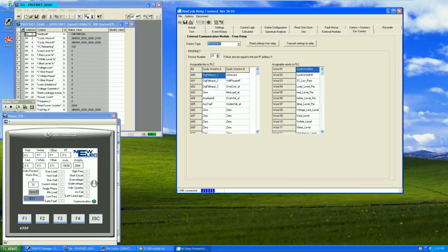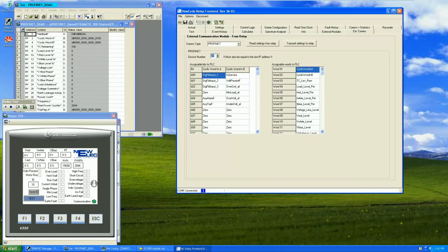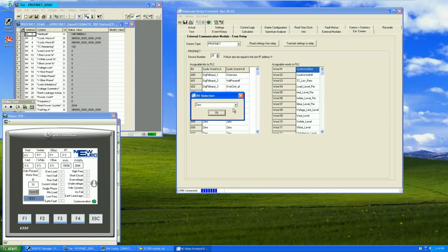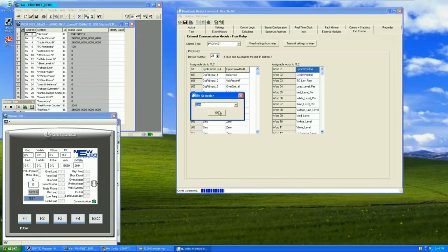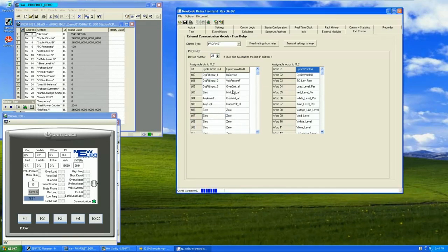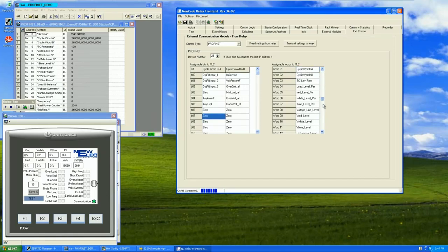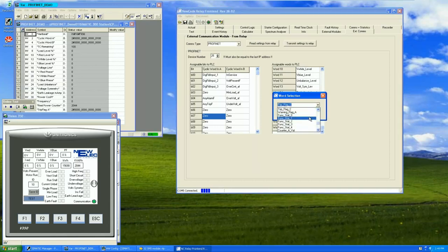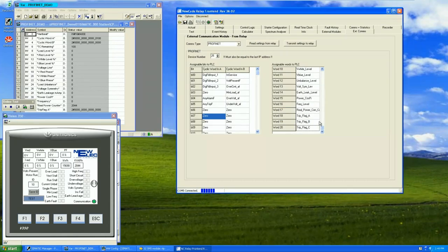A NewCode relay and frontend is needed in order to configure the PROFINET slave device. A PROFINET slave device does not retain its settings but rather gets its settings from the NewCode motor protection relay. This allows the swap out of the PROFINET module without the use of the frontend. In the NewCode relay underneath the External Comms tab, PROFINET needs to be selected. After PROFINET is selected then the address can be assigned to the NewCode relay. This address must match the device name inside of the PLC which will be shown later.